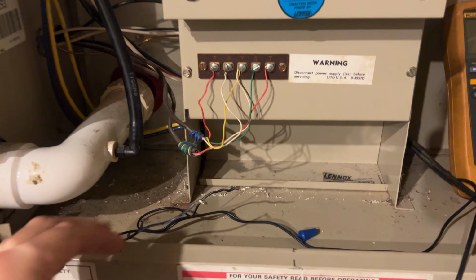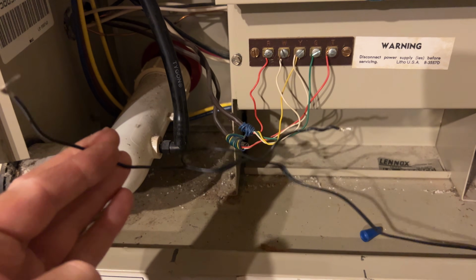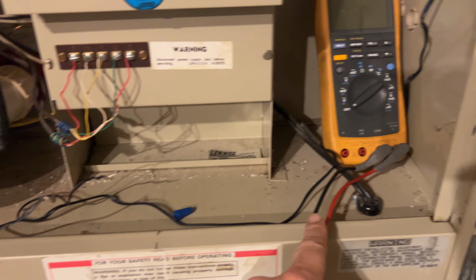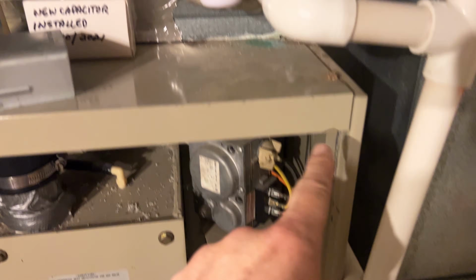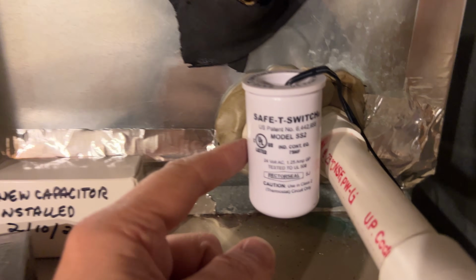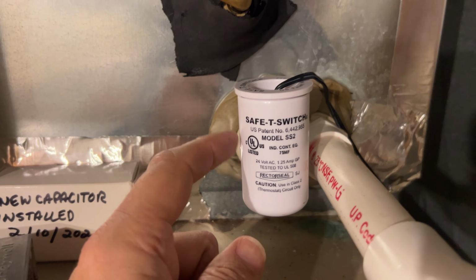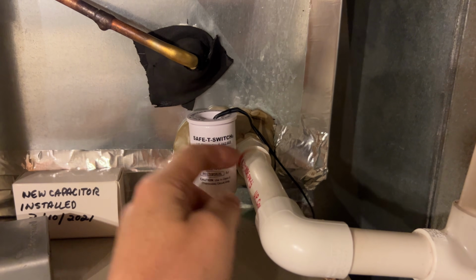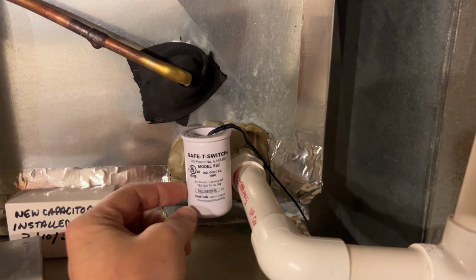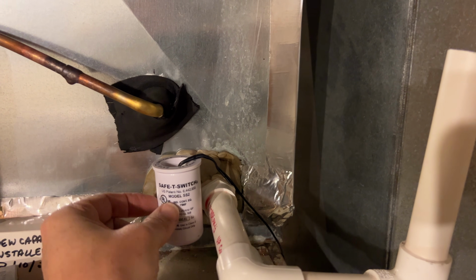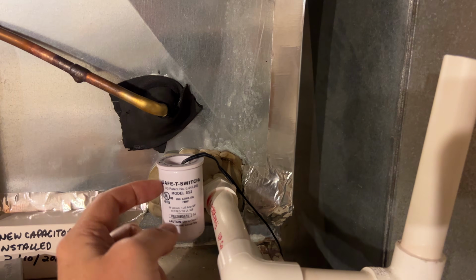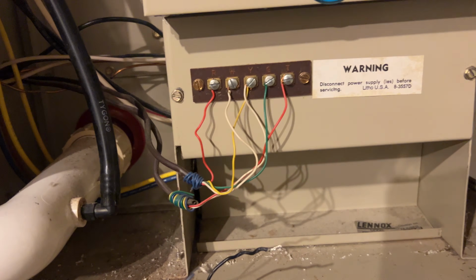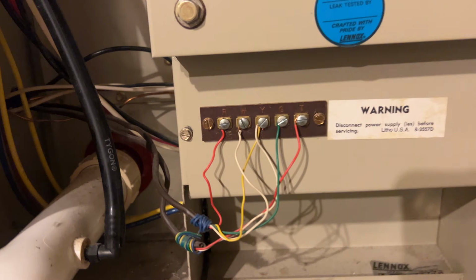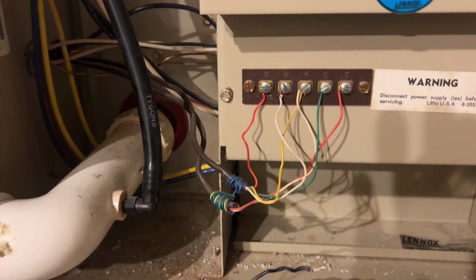Okay, so I've temporarily bypassed this safety switch right here. This is a switch that runs up here, and it will detect when there is a clog in the AC drain line. So if this fills up with water, it will shut this off, it'll break the switch. So that's good to have, but I bypassed it for a second because I wanted to take it out of the circuit. So I've got my red wire going direct here now.